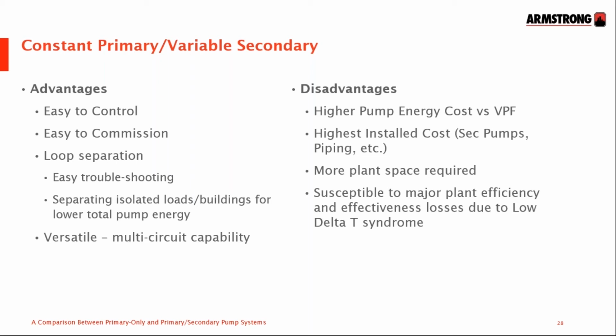The downsides of constant primary, variable secondary is that it does have more energy costs than a variable primary pump system. Also, likely if it's using constant speed chillers, more chilled water energy, because the chillers will be operating at part load at reduced efficiency compared to variable speed chillers running at higher efficiency at part load. It costs more because you've got more pumps, you need more plant space for it, and it's more susceptible to low delta T syndrome. This is when the secondary pumps outrace the primary pumps and pump warm water back into the zones, and then the chillers start up and the towers have to catch up, which wastes a lot of chiller power and towers as well. So those are the downsides of constant primary, variable secondary.